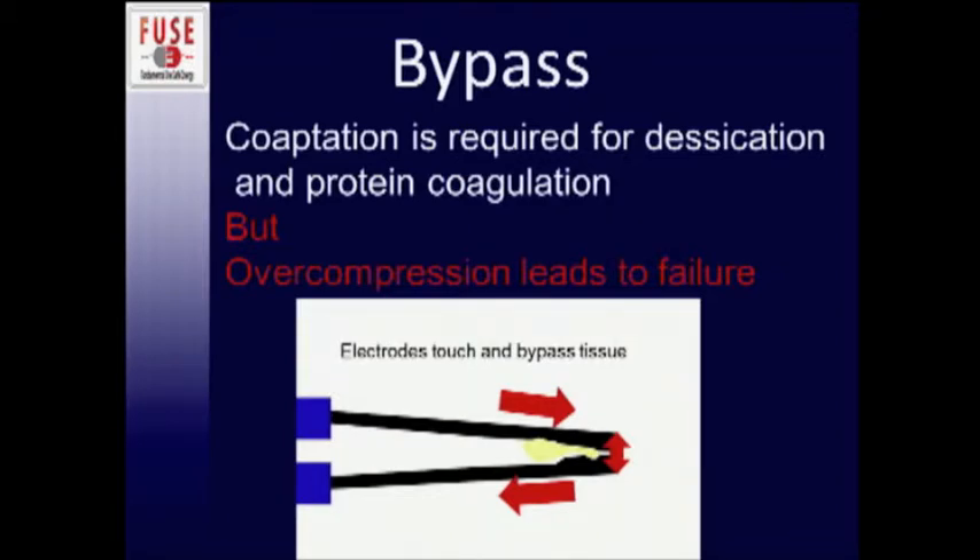To make bipolar work effectively, you have to adequately coapt your tissue together — bringing the vessel walls together to get adequate tissue desiccation so it stops blood flow, preventing the cooling effect blood traveling through can cause. However, coaptation with standard bipolar devices can be inconsistent. One problem can be over-compression, where you squeeze the tissue to a point that the two electrodes actually touch. The electricity then bypasses the tissue altogether and circulates between the electrodes, giving the surgeon a false perception of adequate coagulation when actually not achieving it.